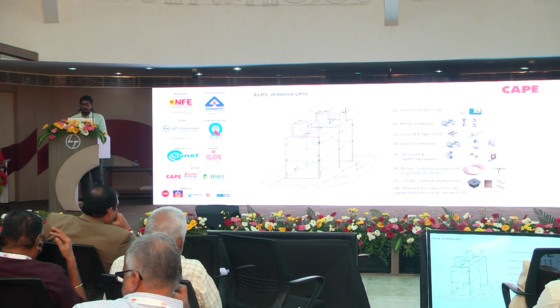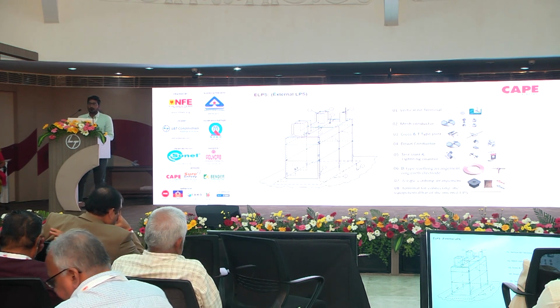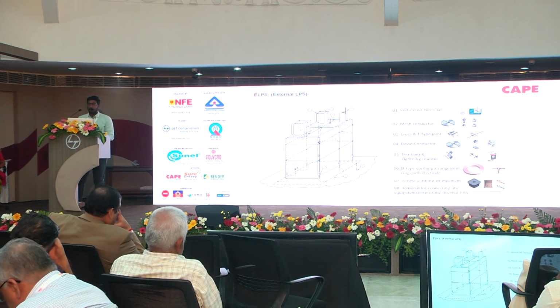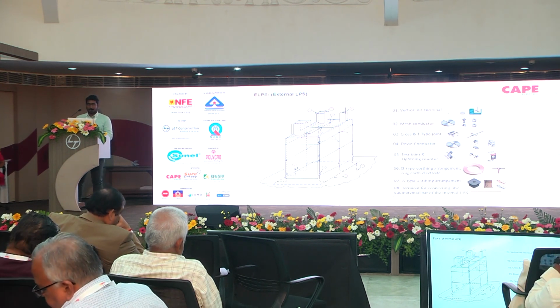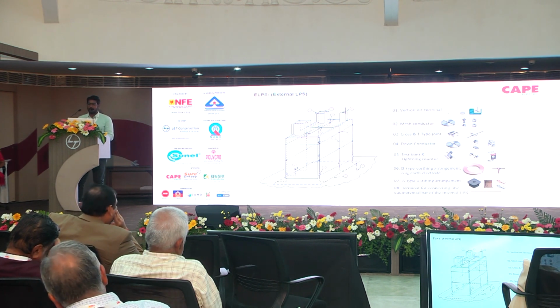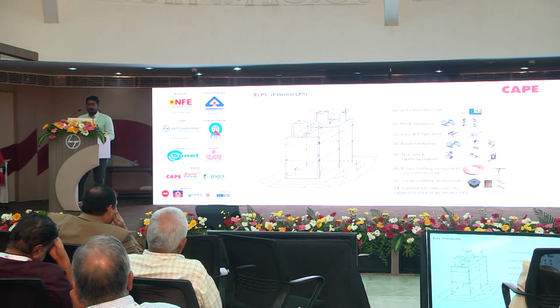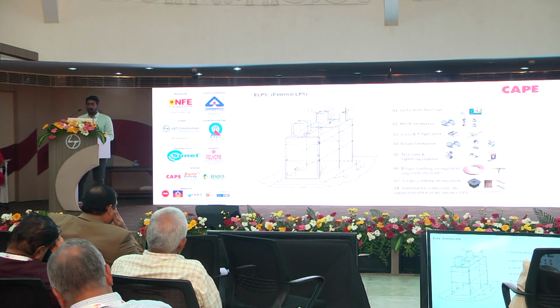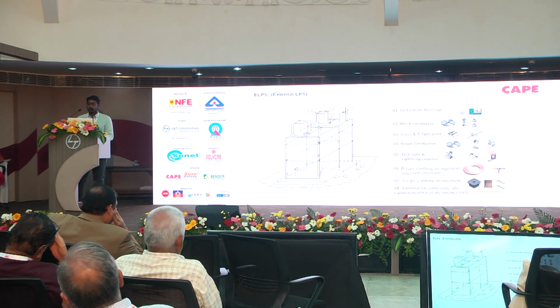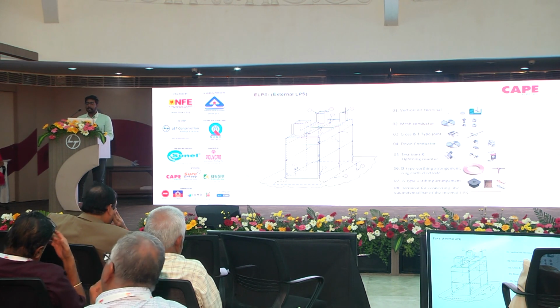So coming to the mesh conductor, in the air termination part we will recommend an 8 mm aluminum conductor, as the standard recommends for the air termination part. And it will be a round type conductor. While routing, it will have a smooth surface, and it will avoid sharp bending or sharp edges at the terrace part, at the corner areas. And the suitable holders have been shown in this PPT. Then an expansion piece will be provided.